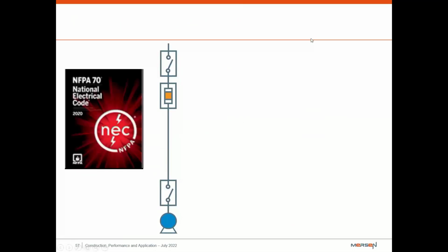Taking a look, we're just going to throw out some numbers right now. We're going to have a 480 volt circuit, 50 horsepower. Your full load amps on this is going to be 65. According to Article 430.32 of the NEC, fuses can provide the overload protection and the short circuit current protection, but they must be sized at 125% of the FLA. So we'll take our 65 and multiply it by 125%, which gives us 81.25, and we're allowed to go up to the next size up, so that's going to be our AJT 90.